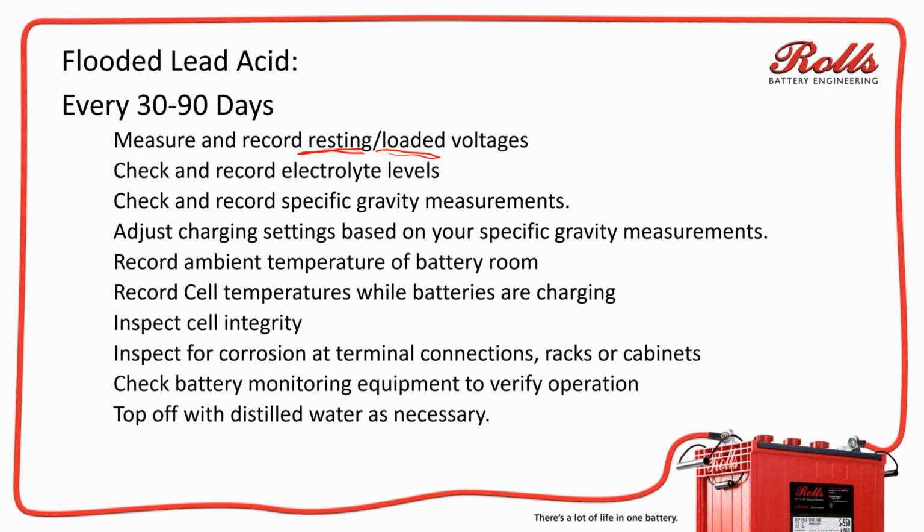Generally, the voltages across all the batteries should drop at close to the same rate. So if you get one battery that's 6.4, one that's 6.3, one that's 6.2, one that's 6.4, one that's 6.3, that's great. That's awesome. I would accept up to about 2 to 4 tenths of a volt difference between the cells or between the batteries. If you see five batteries at 6.4 or 6.2, and then one battery drops all the way down to 5.4, you've definitely got an issue developing there.